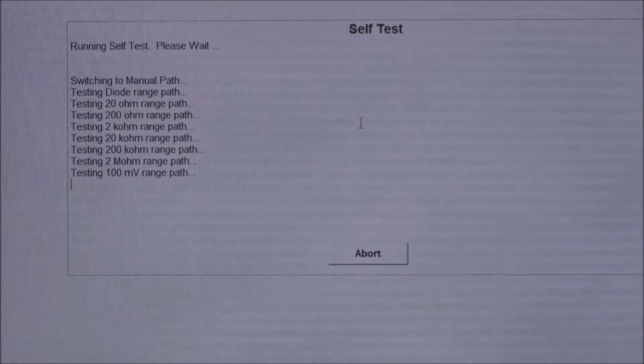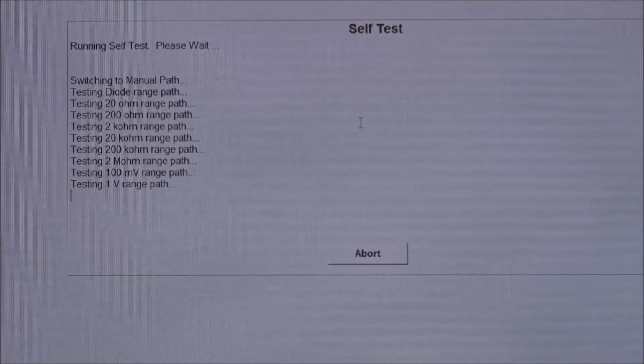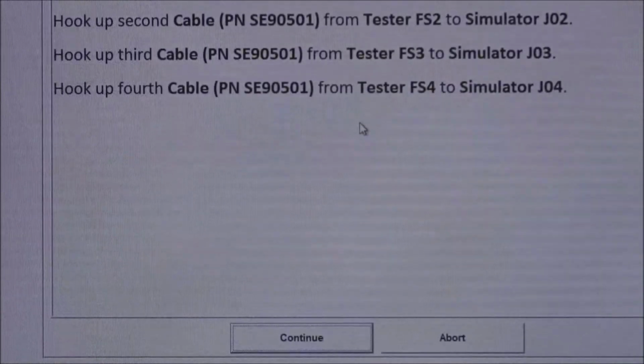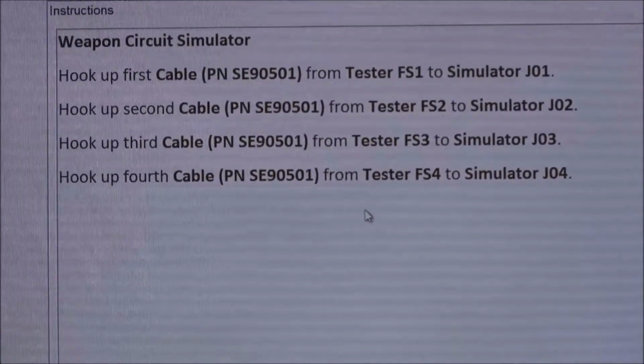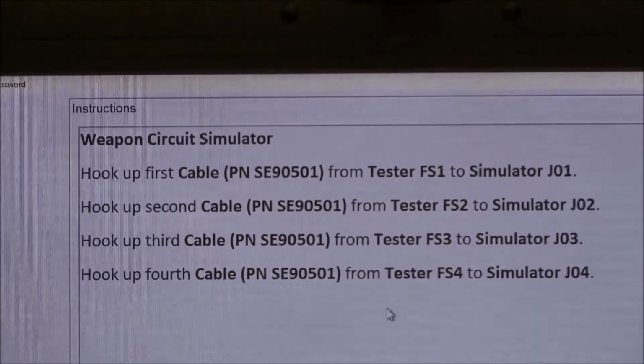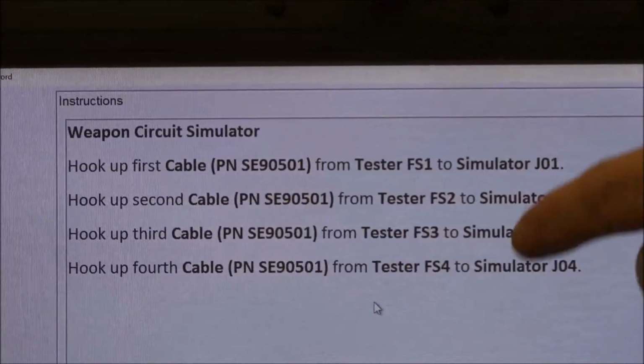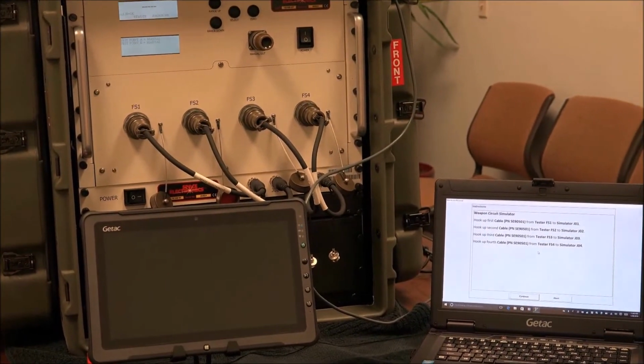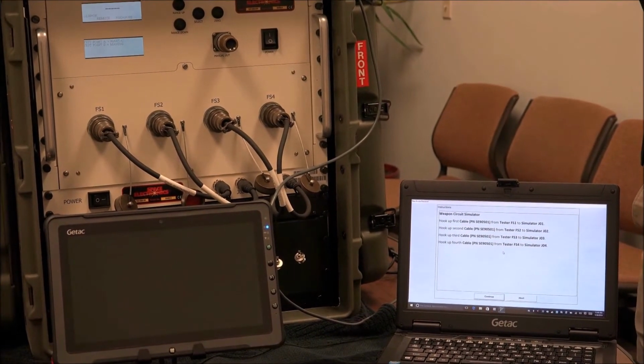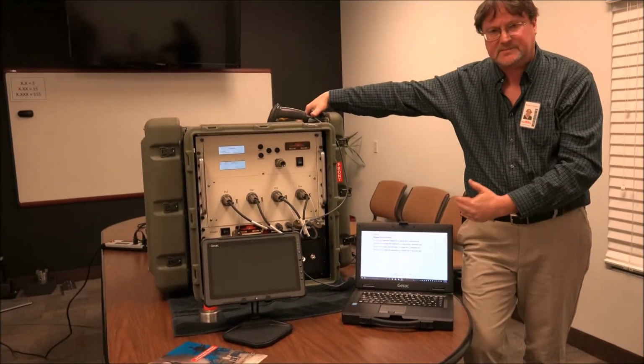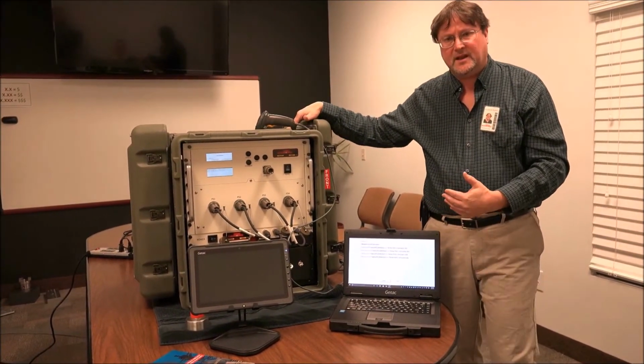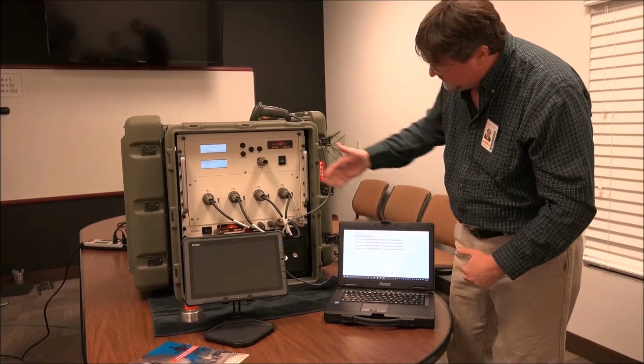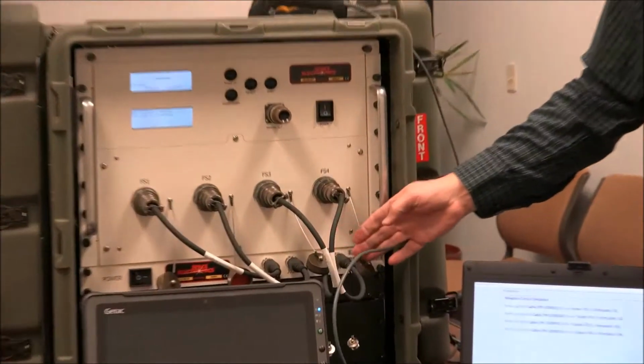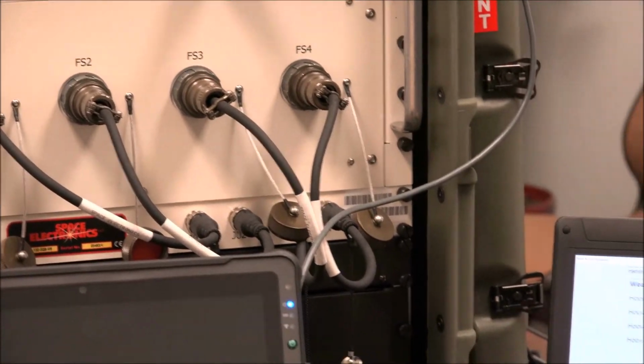Now, the first one of the day, we would plug it into our verification box to verify that the equipment is working. From then on, we'd connect it to the weapon. These prompts are completely controlled by you. So everything that you see here for text is in a rich edit text file that you as an engineer can change to define exactly the instructions you want your operator to follow. So you can mimic your test procedure as closely as possible here to help clarity and understanding of your operators. I've basically got all of them connected, all of them wired, and I'll hit enter to continue.